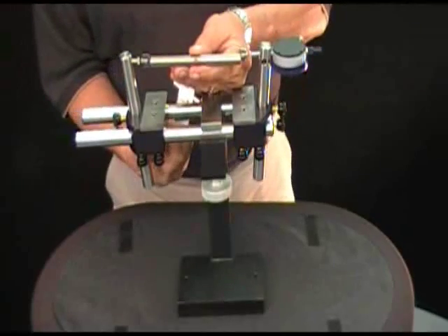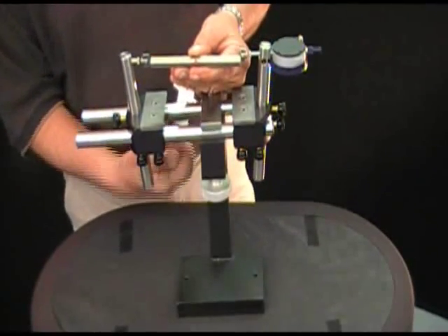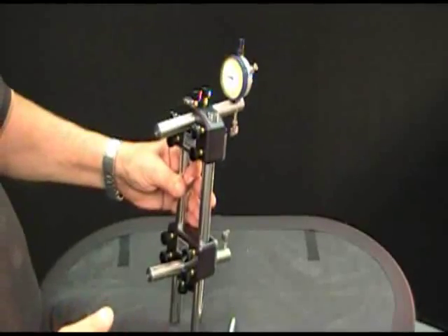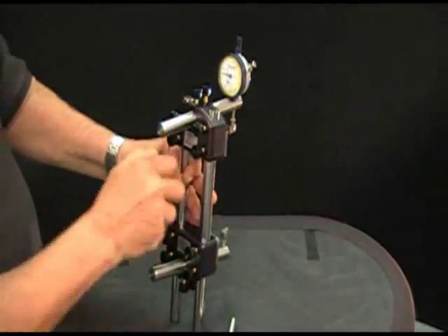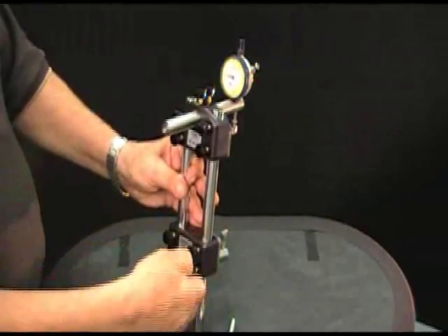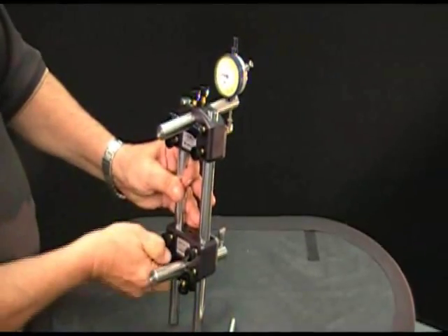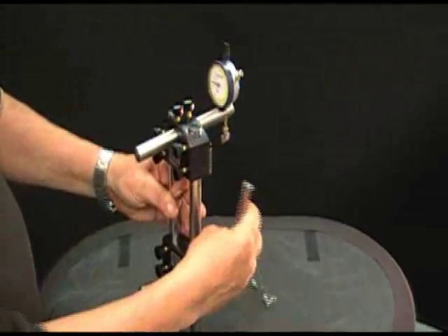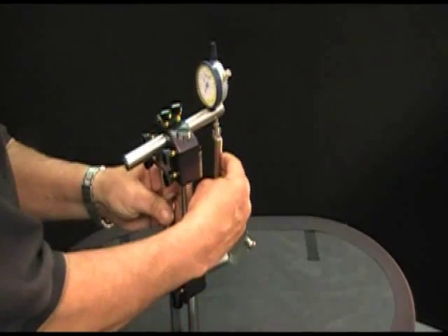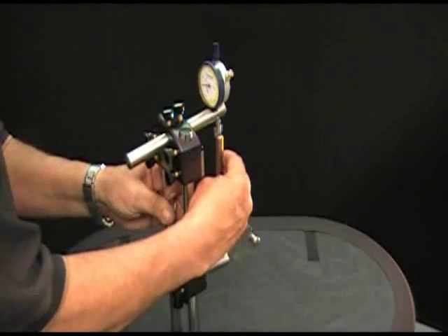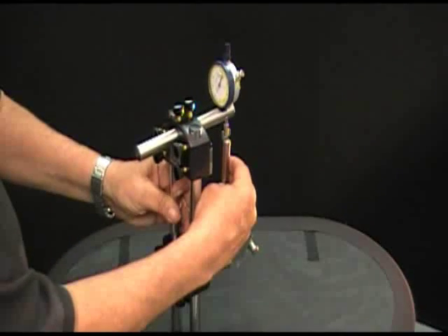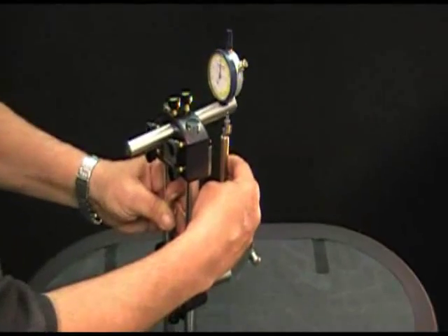Next I'm going to take it off the stand. Now I take the MRP2001 off the stand so that I can make sure that all eight of the locking knobs on the blocks are tight because that keeps the blocks from moving. Then I take the A part of the standard and then set it in between the upper shoe and the lower shoe and I sweep side to side and in and out until the dial reads zero. Then I lock my bezel.